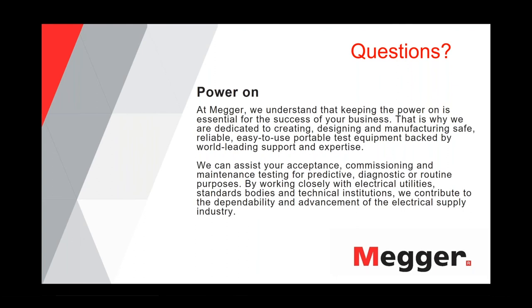All right, thanks. Robert, can you explain why cosine waveform cannot be used for testing? Yes. Well, it can be used for testing, just not for tan delta. So as Henning already explained, with the cosine rectangular waveform, you have an advantage that you are able to measure leakage current. You cannot measure leakage current with the sinusoidal wave because there is no leakage current defined. At any point of the curve, you have a different gradient, so you cannot define this.